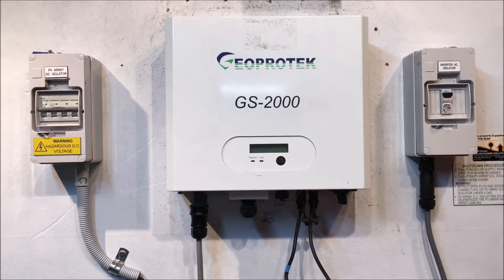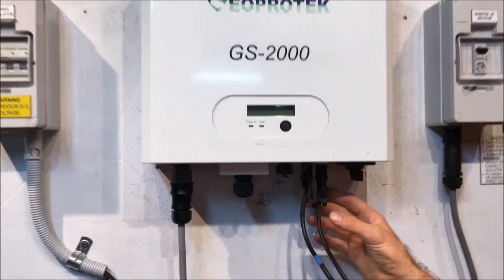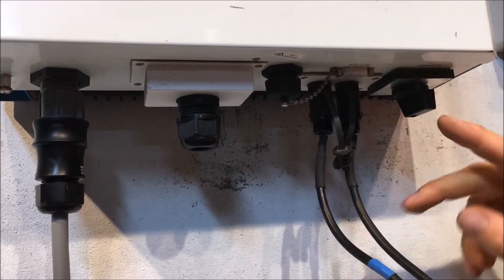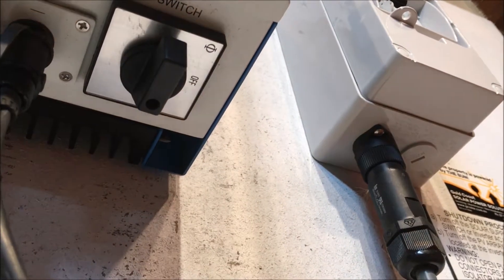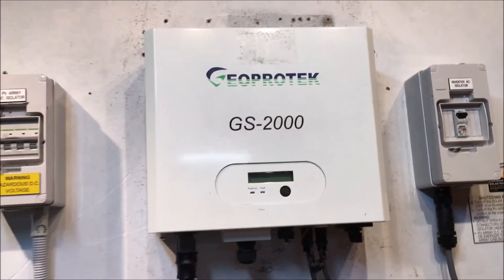One is that the plugs on the inverter on the DC side are actually plugged in and connected correctly. Also, in the case of the Geoprotek, we've got a switch under here — a DC switch. You can see the 'on' position is at the back there, so it should be facing 'on'. Make sure it is in the on position.